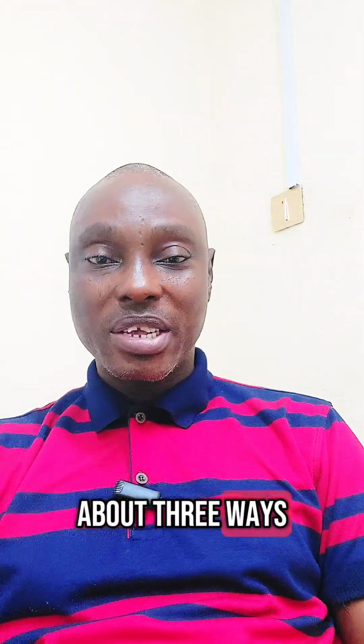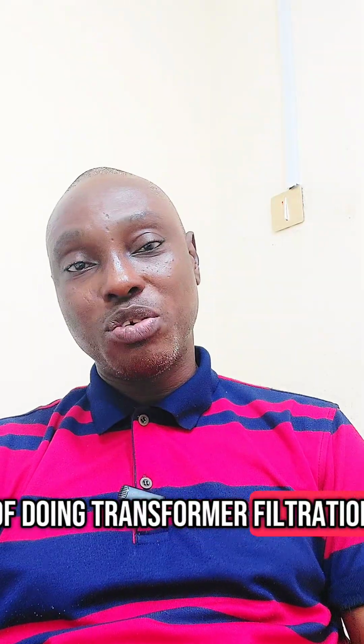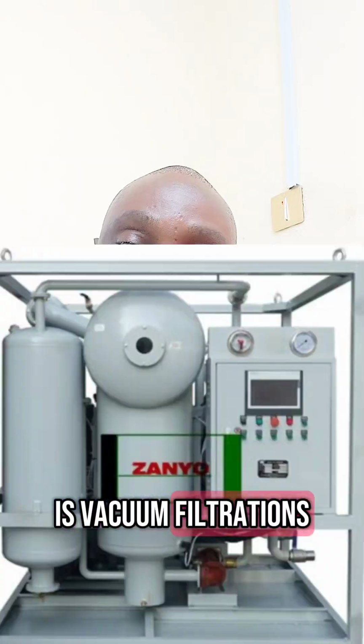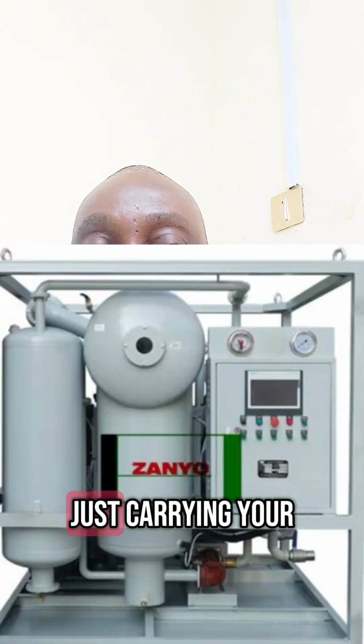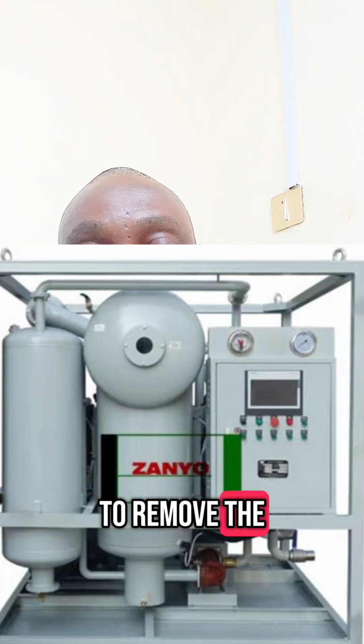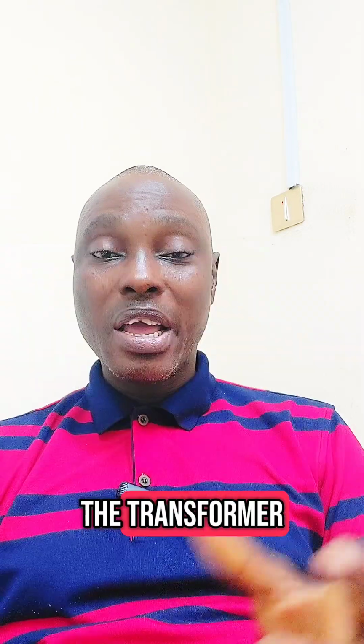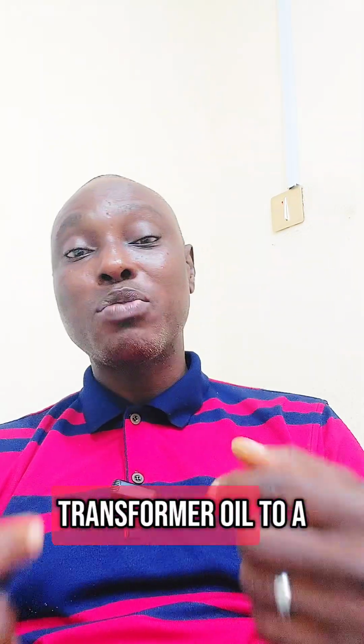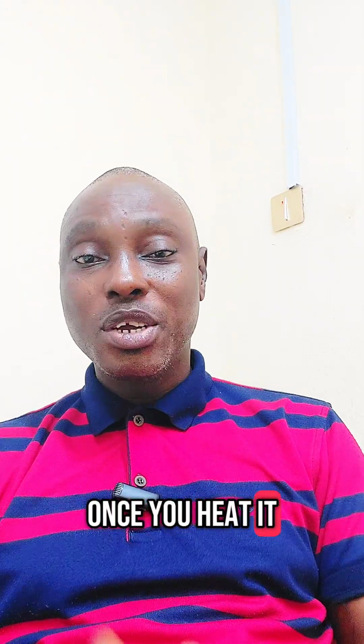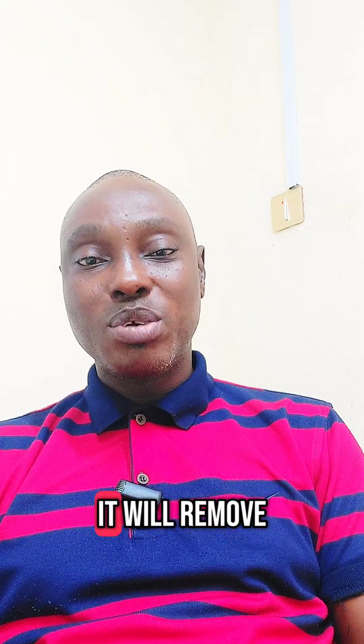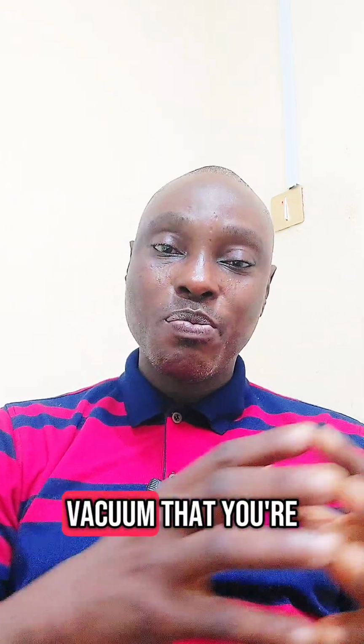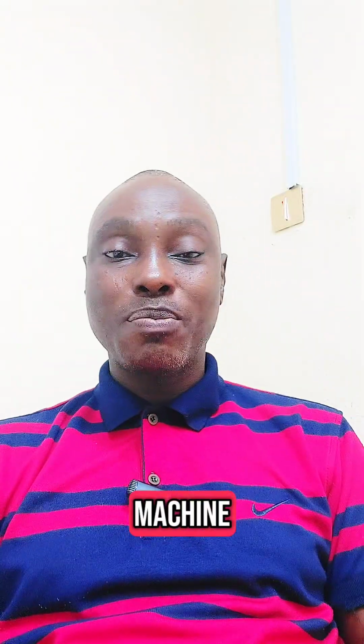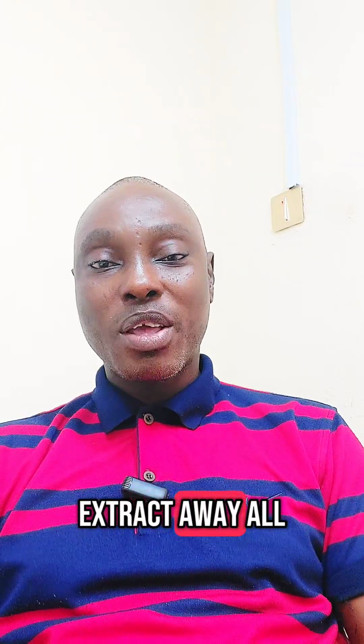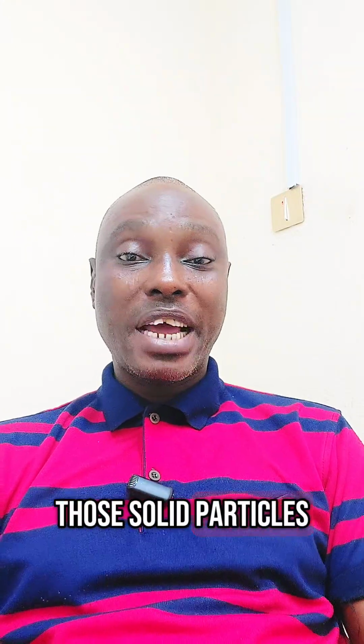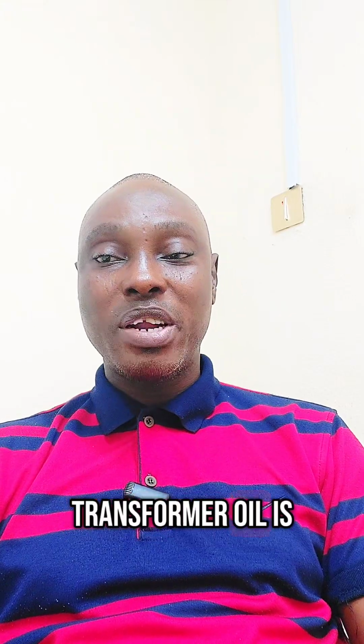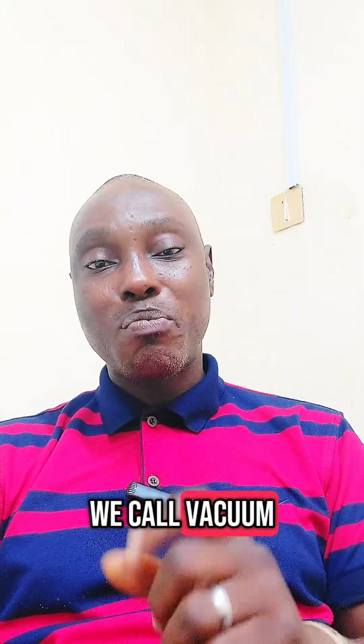So we have about three methods of doing transformer filtration. One of them is vacuum filtration. So what is vacuum filtration? Vacuum is just treating your transformer oil to remove the gaseous part or moisture from it. How do you do this? You heat the oil to a certain temperature. Once you heat it, some of the moisture inside it will be removed. Then you pass it through a vacuum machine, which you are seeing on the screen now, whereby it will extract away all those solid particles that you don't need. Then the transformer oil is good for use. That is what we call the vacuum method of filtration.